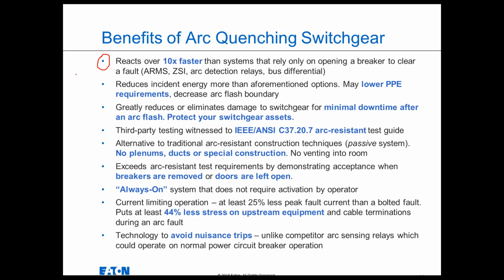So what we did is we developed a system that operates a full order of magnitude faster than systems that rely on a power circuit breaker to clear the fault. And when you reduce your clearing time by an order of magnitude, you can reduce your incident energy by a full order of magnitude. And if you're reducing your incident energy by 10x, that may enable you to lower your PPE requirements. You may be able to decrease your arc flash hazard boundaries. We actually reduced the clearing time to such a low level that we were able to reduce the incident energy to such a low level that damage to the switchgear in the event of an arc flash is greatly reduced or completely eliminated. And that really gives you two main benefits.